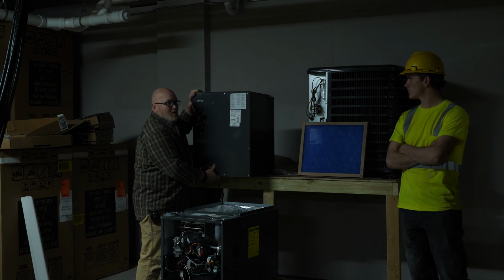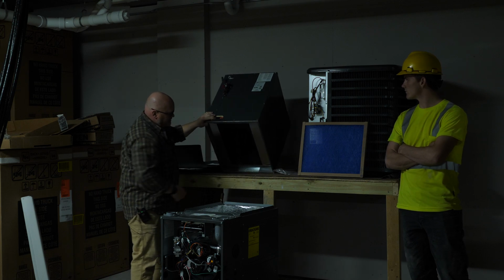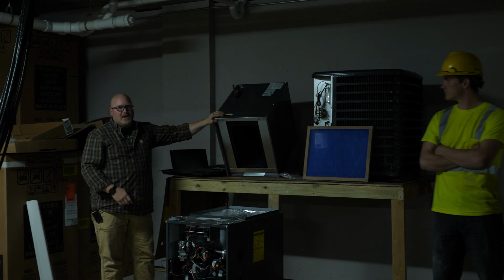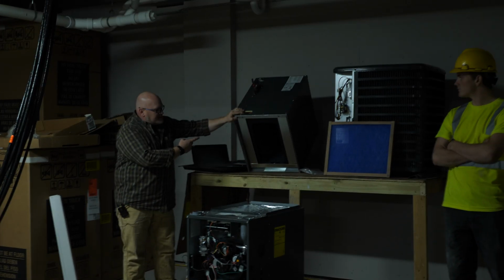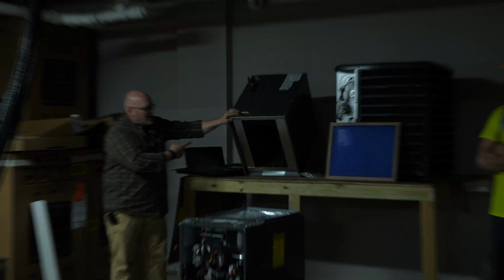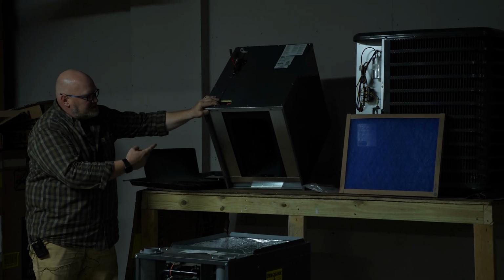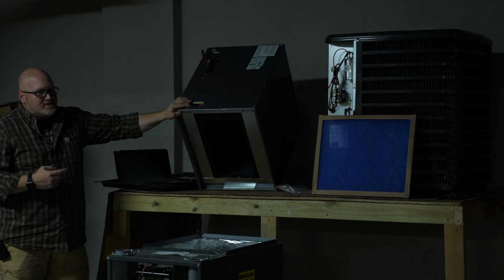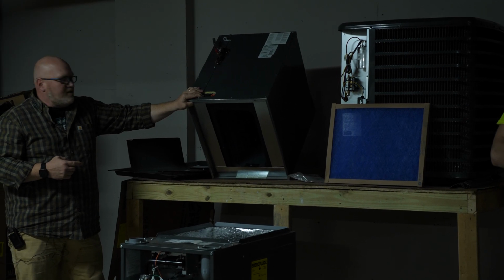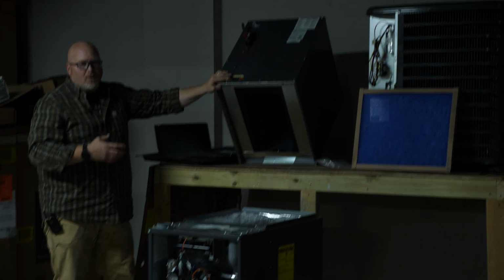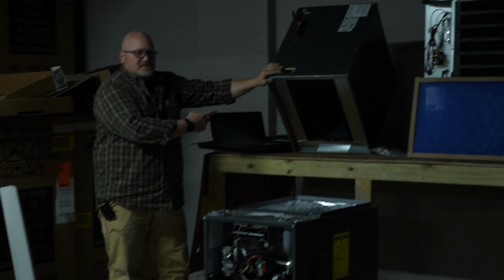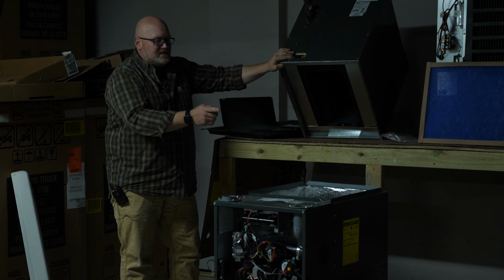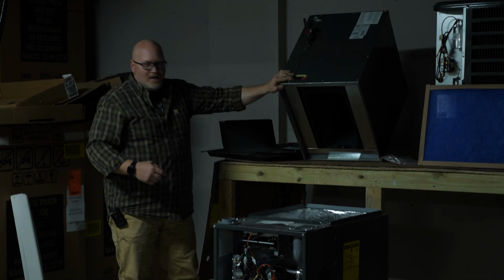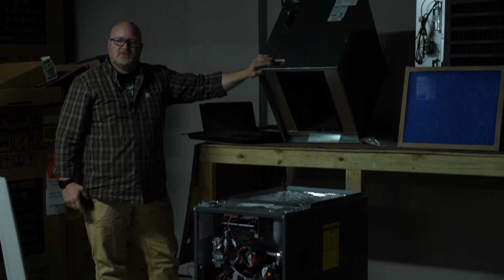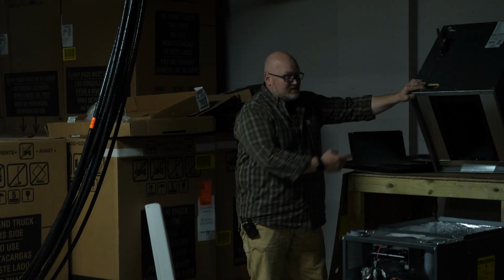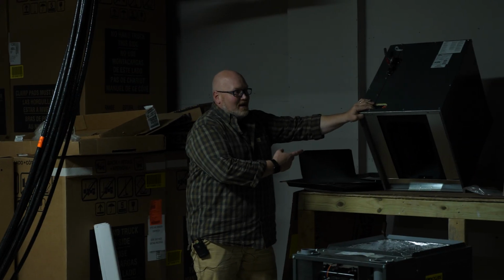And this one's even more of a pain in the butt to change out. And that is the coils and the bottom of this A coil. So the bottom of this A coil, this evaporator, is another whole set of fins and coils that act just like a filter. Now, I have pulled hairballs the size of squirrels and cats out of these things because at some point someone decided it was easy enough to take the filter out and not replace it and then use your A coil as a filter, which it is not designed to do. And to get to this is not a fun task, is it, Dylan?